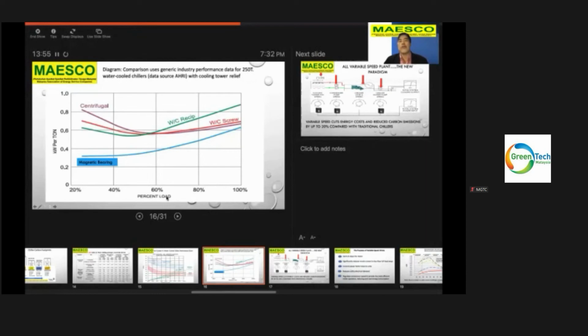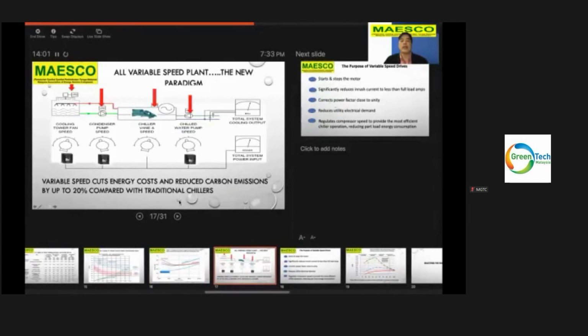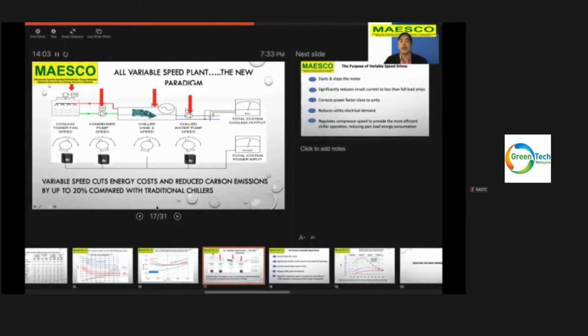You may ask, what about for those old chillers? For old chillers, what we recommend is you can install variable speed drive. You can install variable speed drive to your cooling tower fan, to your condenser pump, to your chillers, to your chill water pump. Variable speed drive cuts energy costs and reduces carbon emission by up to 20% compared with all traditional chillers.